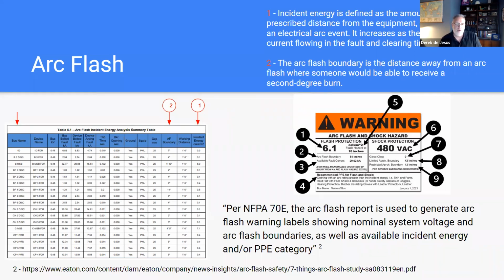As an owner, we were trying to get to the point where we could work under a temporary label during construction. We took the worst case scenario and applied that to the whole gear, so that in the electrical vault, we treat the whole space as one boundary, at minimum the maximum PPE requirements of that space. That allowed us and the contractor to move forward with energization. We were getting little plastic sleeves, putting them on gear, and sliding in this temporary arc flash label so we could do our energization.